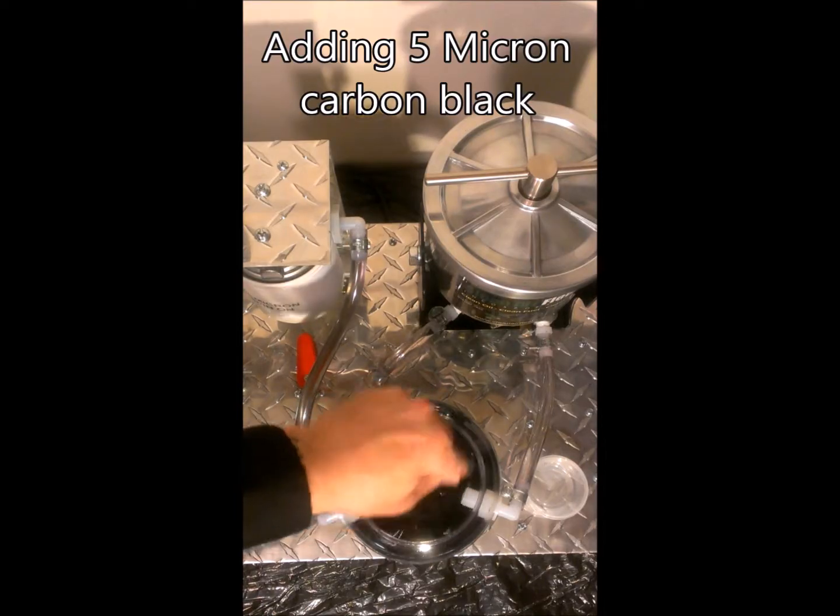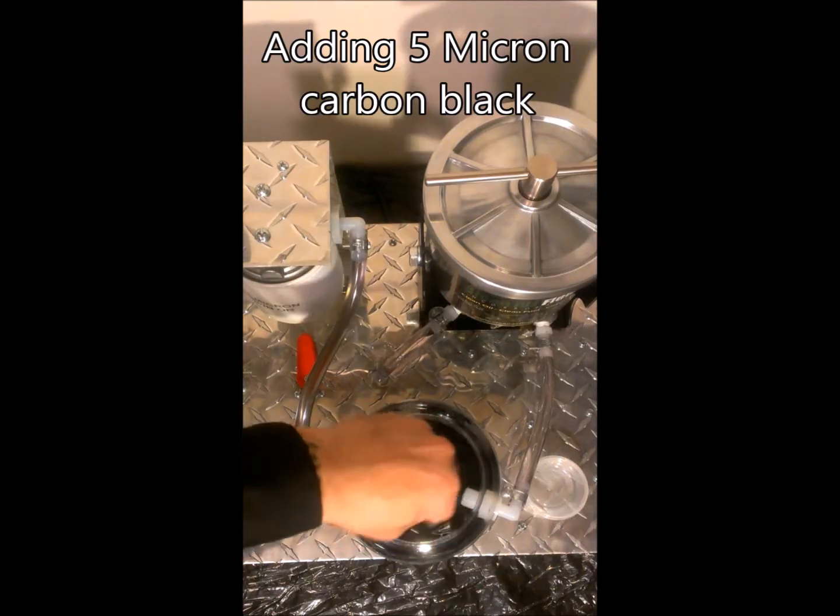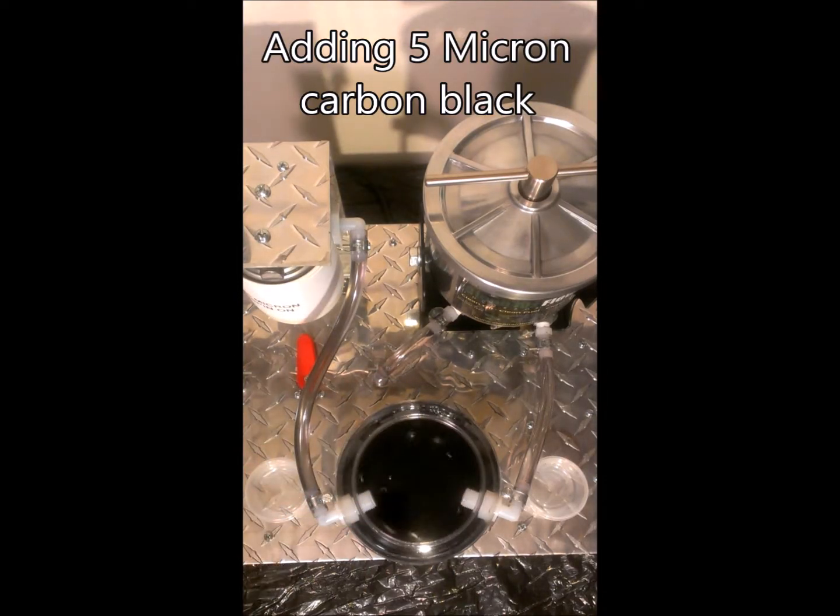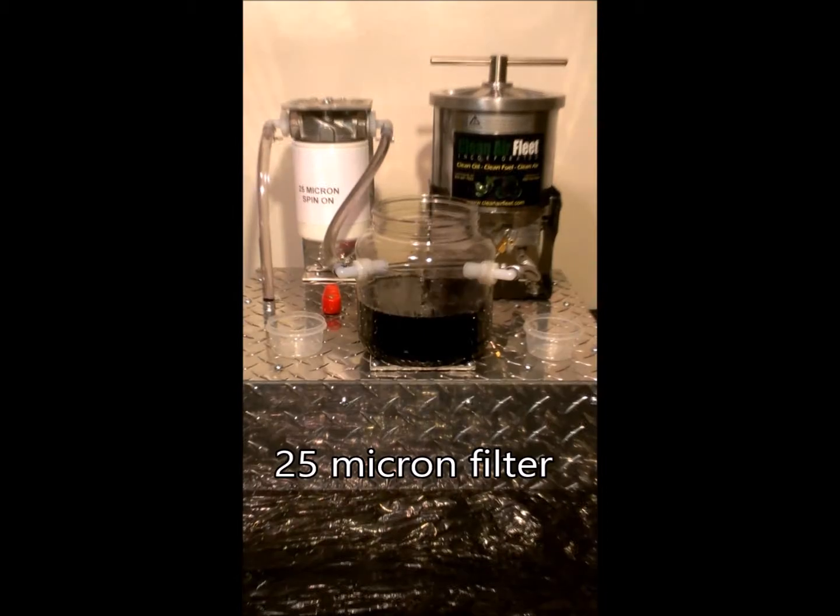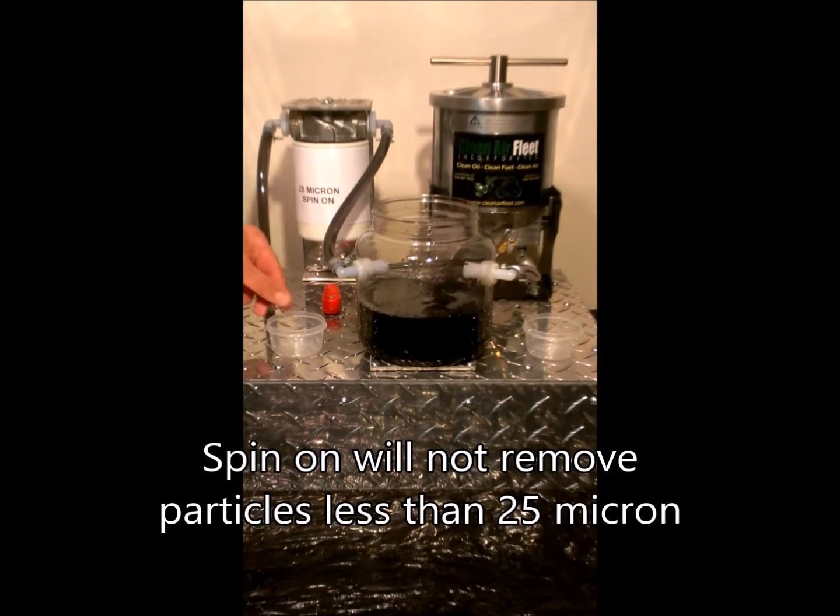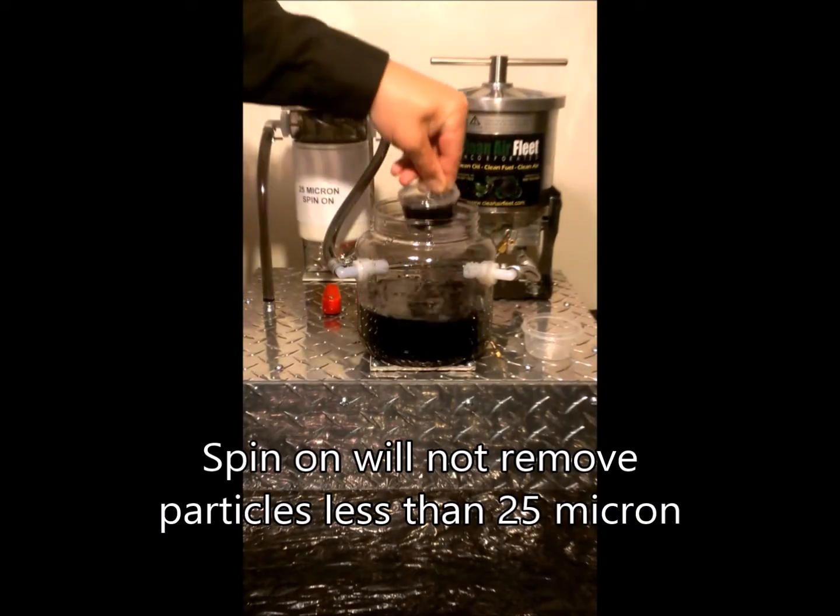Next, you will see how the 25 micron spin-on is not capable of removing any of the black. Now we will pump the oil through the 25 micron filter. See the carbon in the oil coming out still black? The spin-on will not remove particles less than 25 micron from the oil.